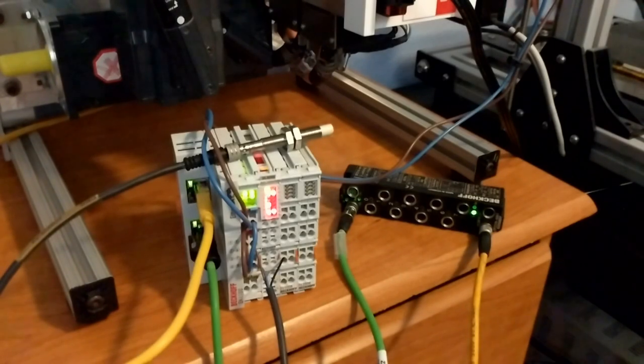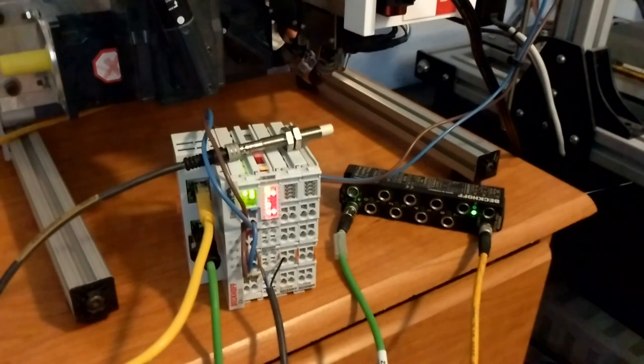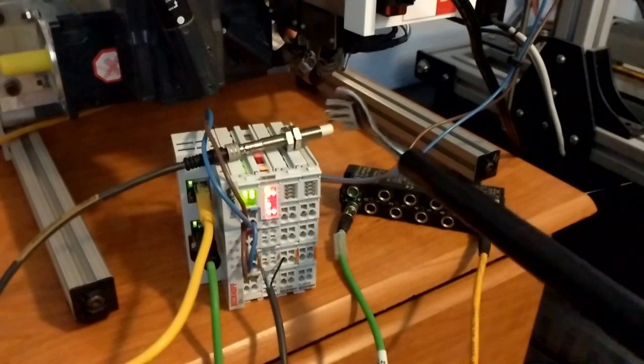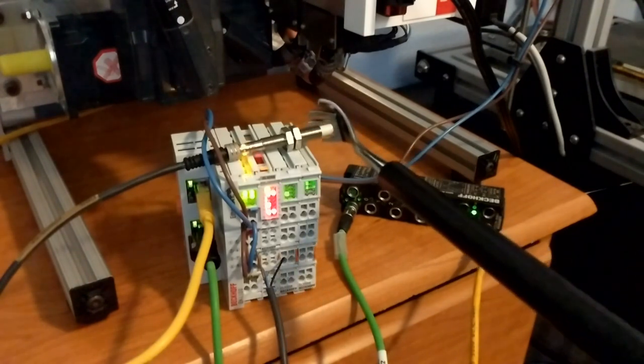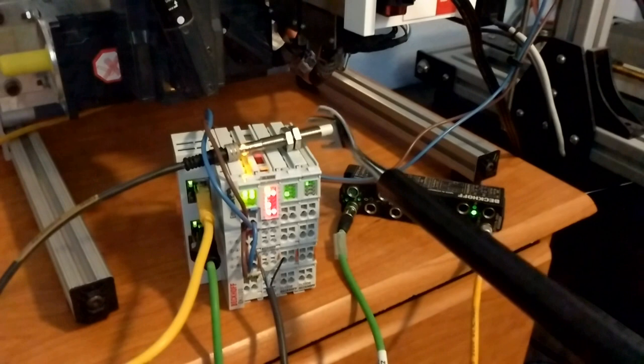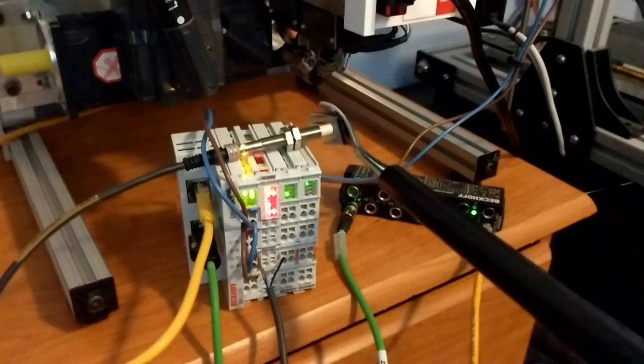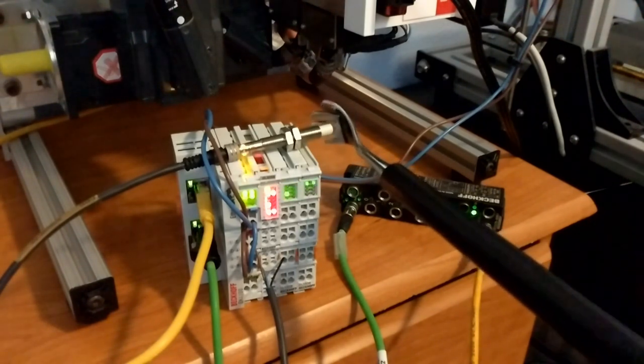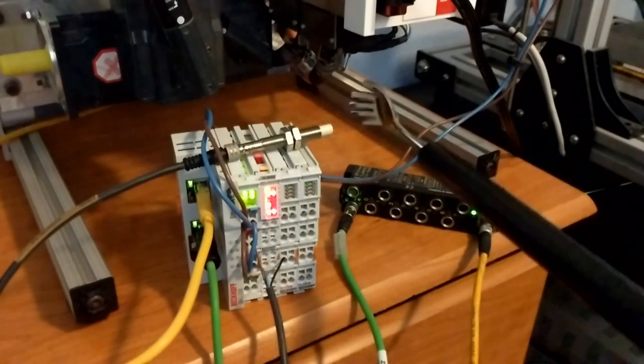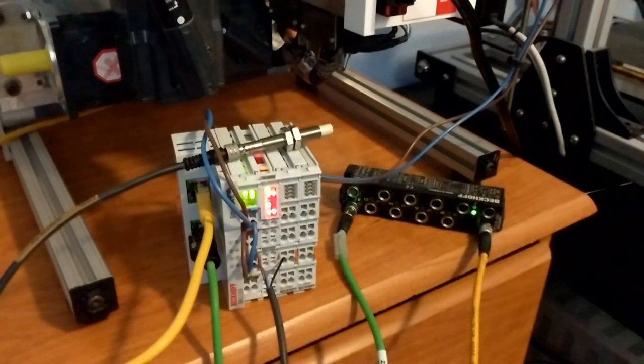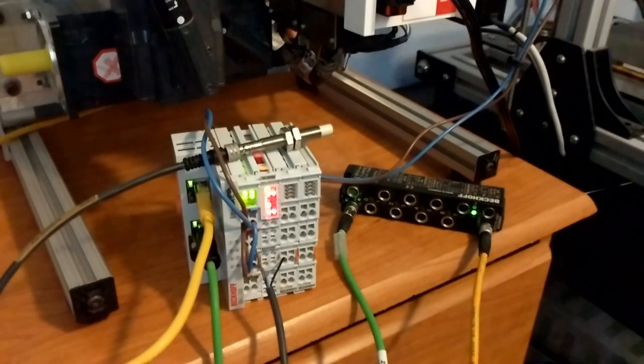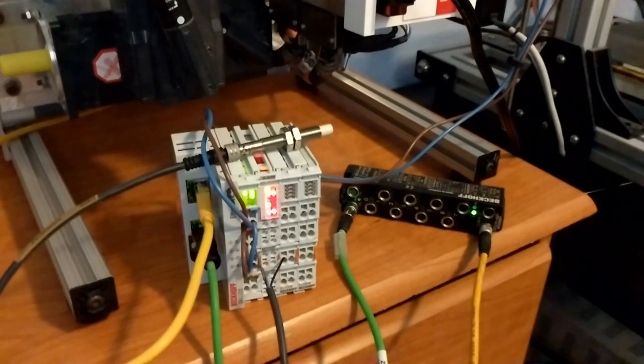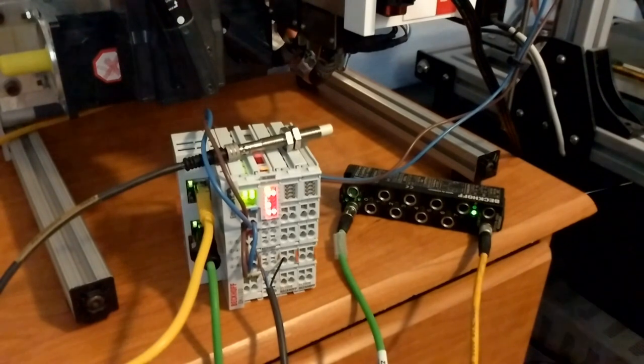All right. So I've situated the proximity sensor right on top of my inputs and outputs there. As I get close to it, you'll see the prox will light up as soon as it senses the metal. And that turns on the slice to the left's input, which then our program tells those four outputs to flicker. So you can imagine this would be analogous to something like a part showing up on a conveyor. And then these outputs would actuate from your program control to fire a cylinder, like a pneumatic cylinder, or turn on a conveyor zone or something to that effect. So hopefully you understand that as a pretty basic I.O. example.